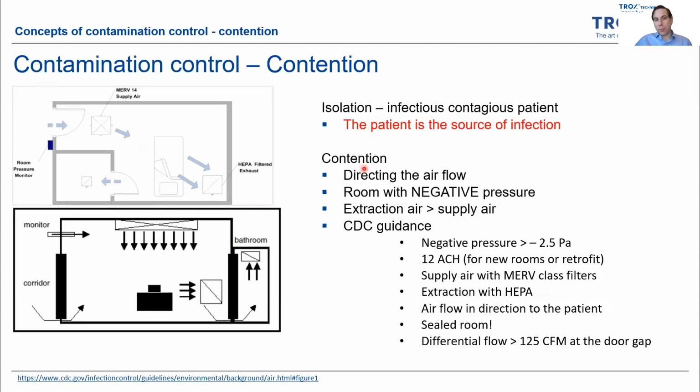The supply needs to be done by air filters. Yeah, we need to clean the air that we are injecting into the patient room. And it goes back to the particles that we saw in the beginning of the presentation. The extraction has to be done by a HEPA filter because that's contaminated air. And then we want to keep this virus or bacteria in this filter.